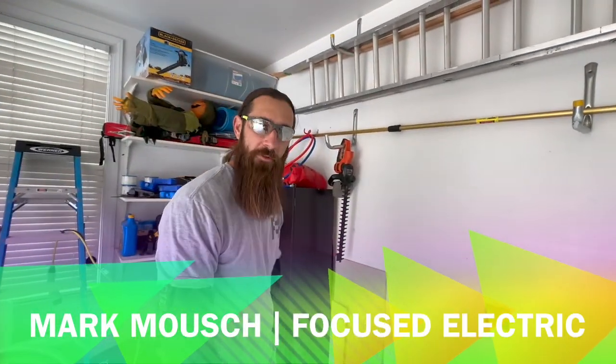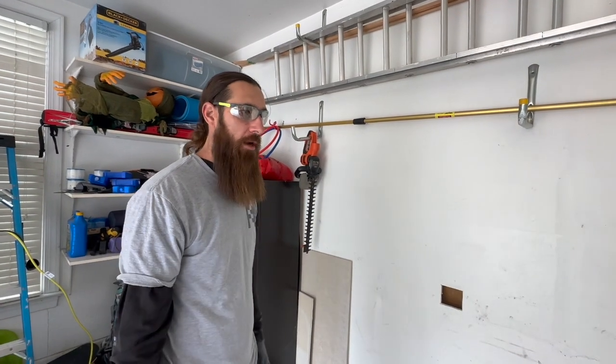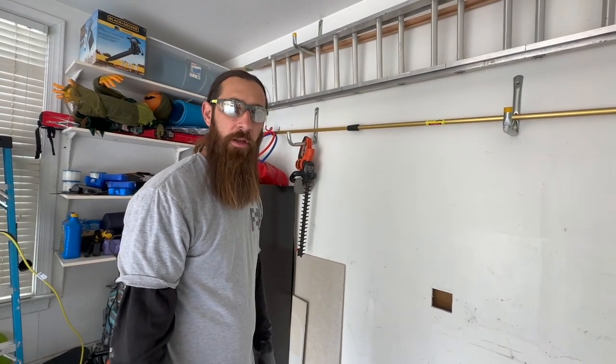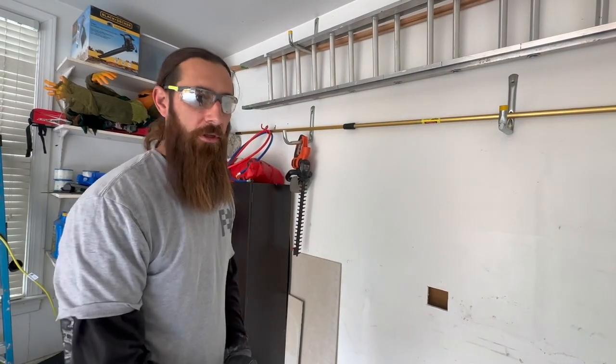Hi, how are you doing? I'm Mark with Focused Electric. We will be installing two NEMA 14-50 receptacle outlets with overcurrent protection — two-pole 40-amp breakers with number eight wire — to maximize at 32 amps for each charging location.